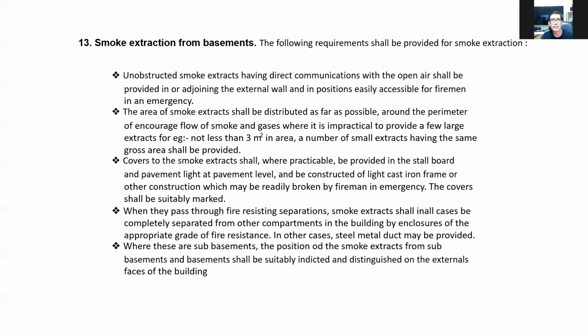The area of the smoke extracts shall be distributed as far as possible around the perimeter to encourage the flow of smoke and gases. Where it is impractical to provide a few large extracts, a number of small extracts having the same gross area, not less than 3 square meters, shall be provided. Covers to the smoke extracts shall, where practicable, be provided in the stall board and pavement lights at pavement level, and be constructed of light cast iron frames or other construction which may be readily broken by firemen in an emergency. The covers shall be suitably marked.